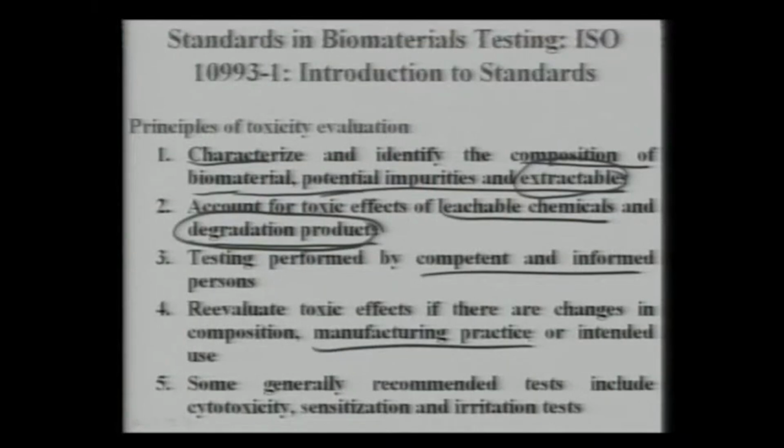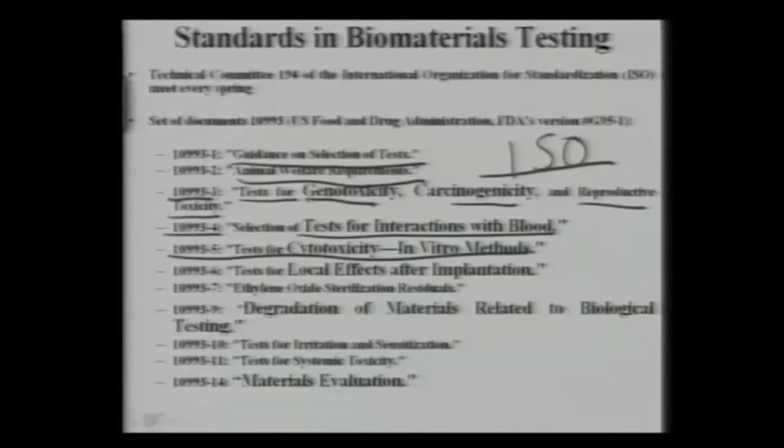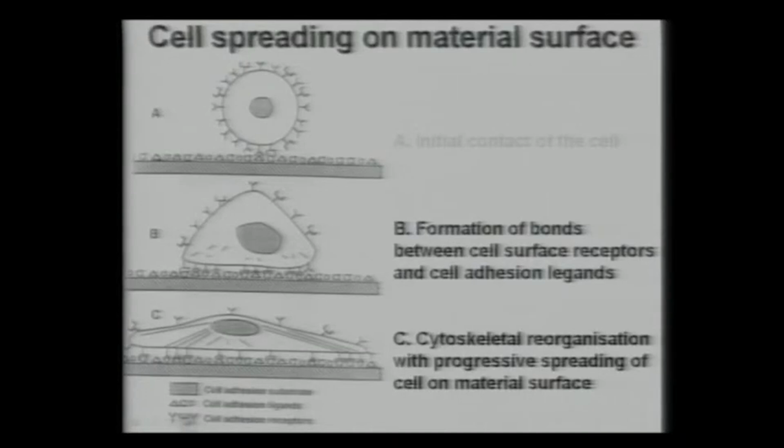Now, some generally recommended tests include cytotoxicity, sensitization, or irritation tests. Now, as I said, the in vitro cytotoxicity, that is the cell culture test, is under the guideline of 10993, and I'll quickly go through what was summarized in the last lecture.